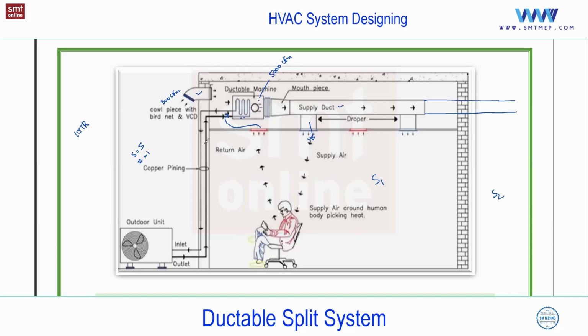And remember, when I use this 10%, or say 10 to 30% fresh air, this is as per thumb rule. So from an interview point of view, we can use this when they ask the requirement for fresh air: as per thumb rule it is 10 to 30% for commercial and residential spaces. Commercial like office, school, mall, etc. Residential, you know. This is just as per thumb rule. But we have a detailed calculation as per standard. The standard can be ASHRAE 62.1, or it can be a Carrier standard, or it can be Dubai Municipal, etc., as per the location or authority.